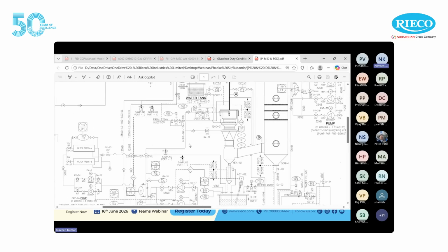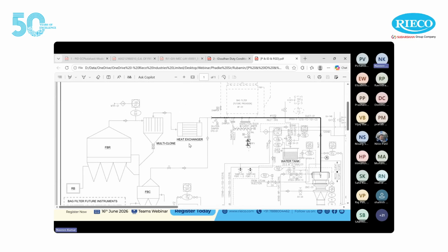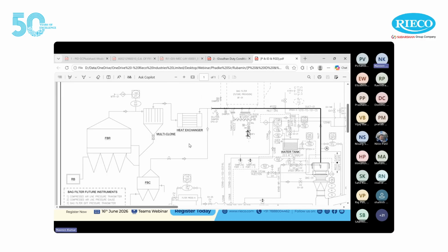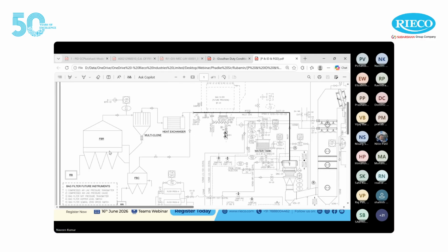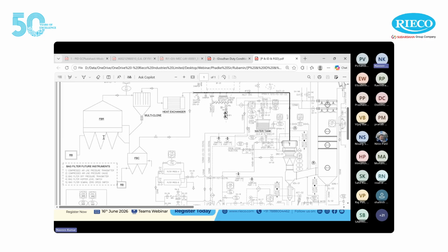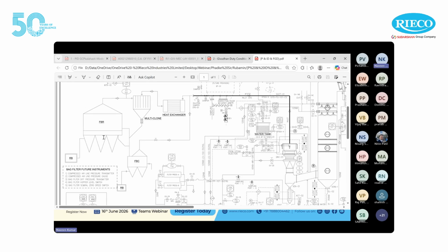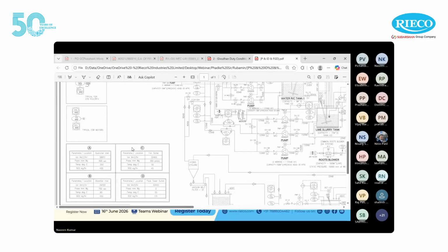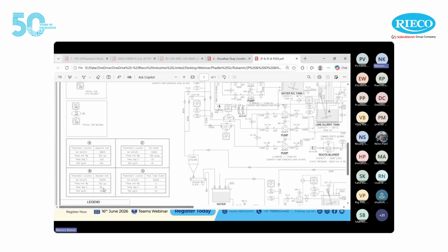So the first part of the process involves roasting of this catalyst, so it's an oxidation reaction, and the gases which come out contain a very high quantity of sulfur dioxide. It is of the order of 5,125 ppm for a gas volume of about 59,000 actual meter cube per hour at a temperature of 250 degrees centigrade. The dust load is expected to be around 5 grams per nm cube.